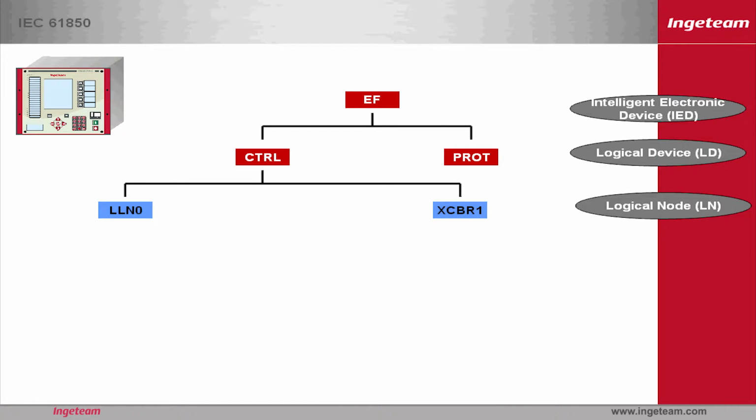On the other hand, given that each device can have more than one element of each type, the logical node's name has a number after it, in a range of 1 to 99 to indicate which of the switches, choppers, digital input and output groups etc. is being represented. In short, 4 letters identify the functional feature being performed by this device, and a number from 1 to 99 identifies the device's element. Additionally, there is the option for all logical nodes to have a prefix in front of the name, which will allow the manufacturer to organize the information, but this is a minimal level of freedom which is in fact not expressed in this case.